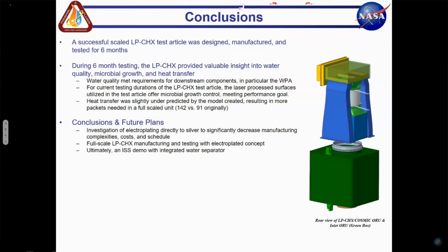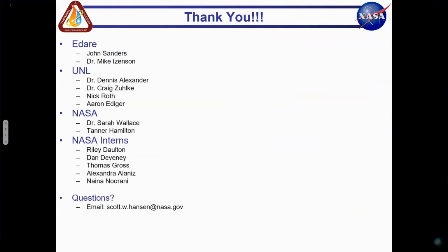So our future plans for this, one of the things we really want to look at is, I mentioned the individual packets are made up of a silver or stainless steel packet enveloped with thermal interface material and silver. We want to look at electroplating silver directly onto that stainless steel packet. That would decrease the manufacturing time, the cost, and the complexities in building up a full-scale heat exchanger. So we want to investigate that and then move into building a full-scale laser process heat exchanger and test it. And ultimately, we have our eyes set on an ISS demo with one of those integrated water separators, either from Paragon or from Sierra Nevada.